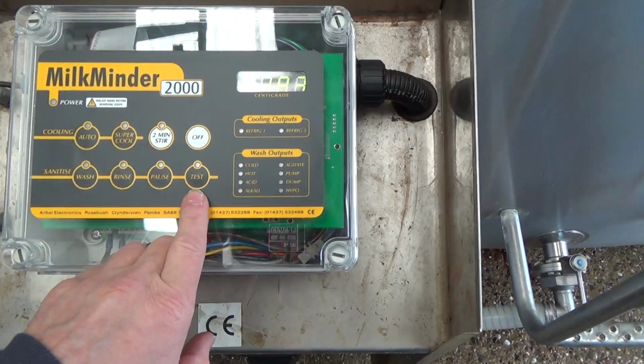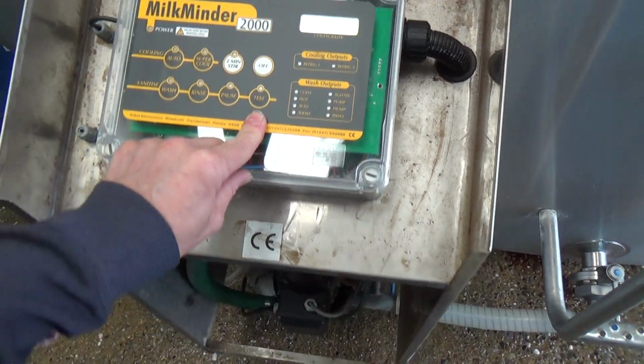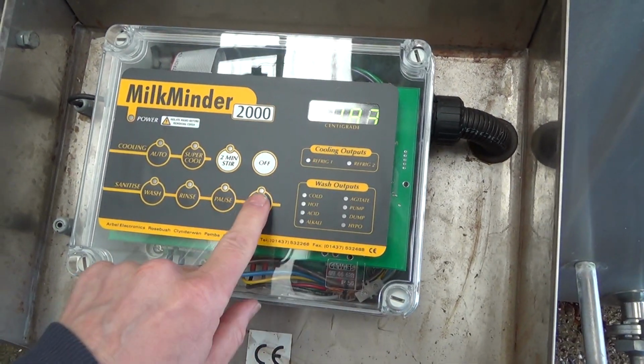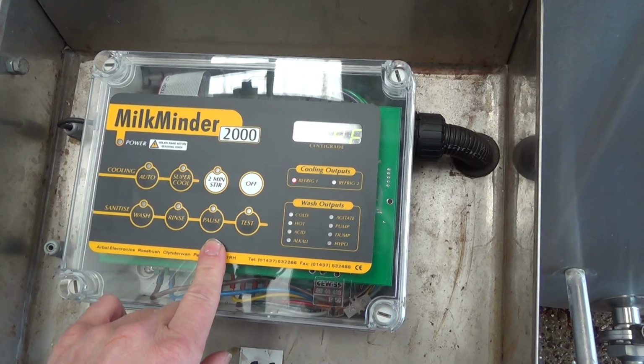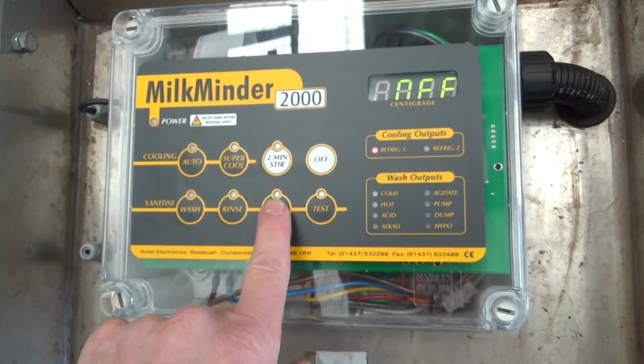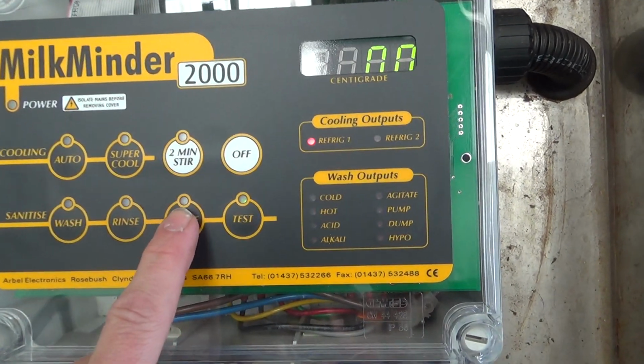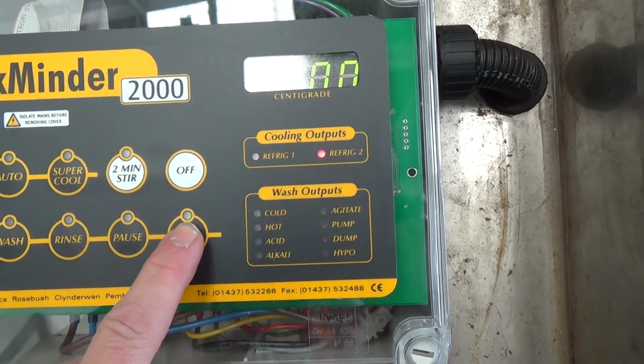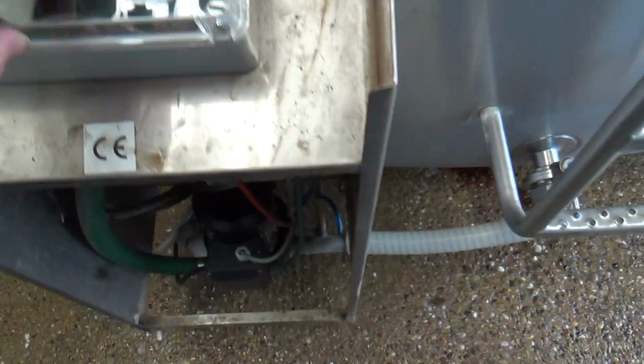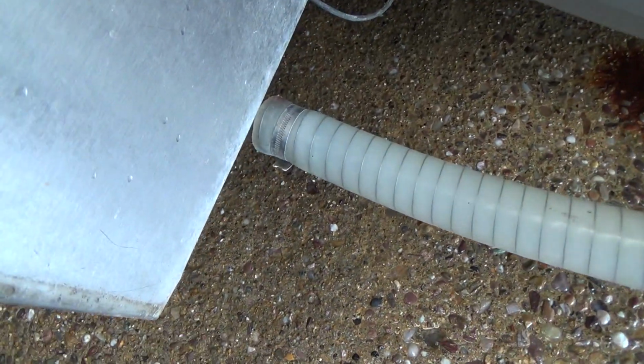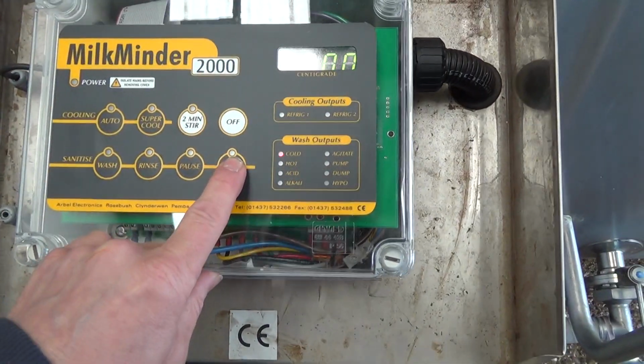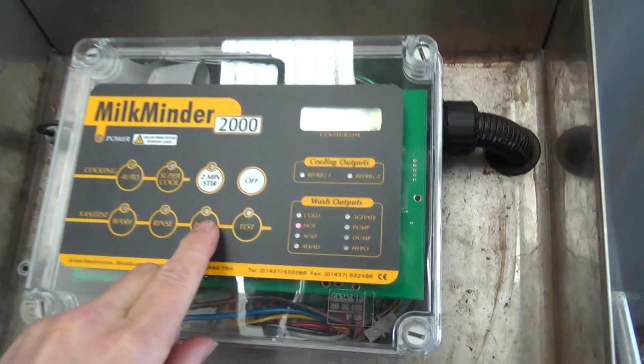Anyway, I was a bit surprised to get here and find it's washed okay this morning. On these you can hit the test mode, and you can scroll through. So we've got compressor, and if you hit the pause button, you can toggle between energising that output and not. If I energise it, you hear the click and the solenoid open. So that's compressor 1, compressor 2, cold valve. That's putting water in. You can see the bubbles going in. I can hear a little pump running off in the distance. That should be hot going in. I can hear that pump whirring. That's getting warm, so that's hot going in.